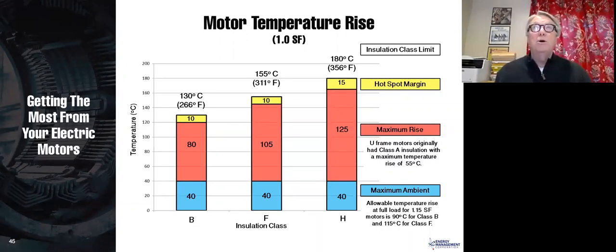Because a cool motor is a motor that runs a long time. It can tolerate some overload. It's just a very good motor. And I highly recommend that you always specify a Class F insulation, but Class B rise. And that is not just me. This is very, very common in the industry. Lots of people do that.